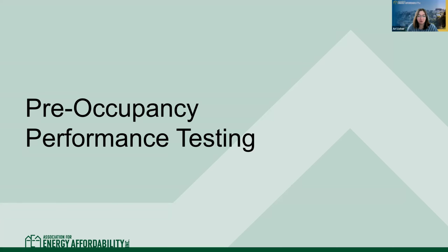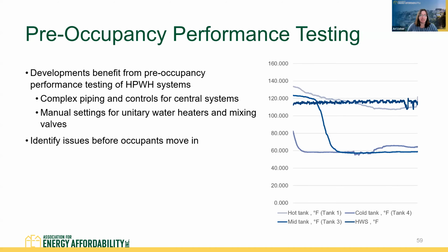Yeah, pre-occupancy performance testing. So once construction is completed, but before the occupants move in, it's going to be a big benefit to the development to do some pre-occupancy performance testing, some lowercase c commissioning of heat pump water heating systems. And this is whether they're unitary or central systems. I think hopefully you've seen that there's a bit of complexity in terms of the piping and the controls for central systems. With unitary systems, there are also manual settings, both for the controls and for mixing valves as well. So for both system types, some pre-occupancy testing is really highly recommended.